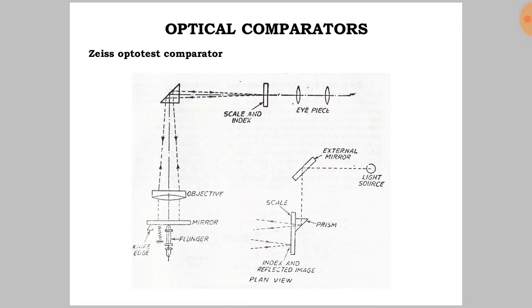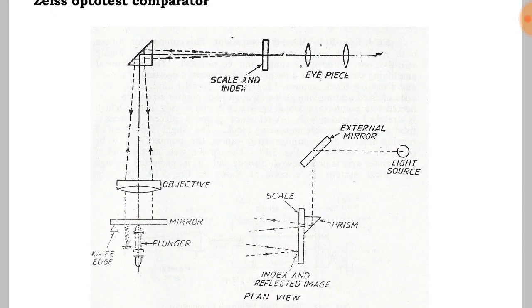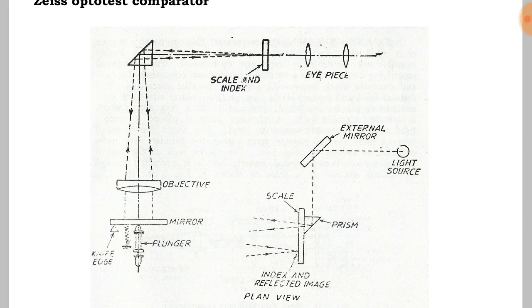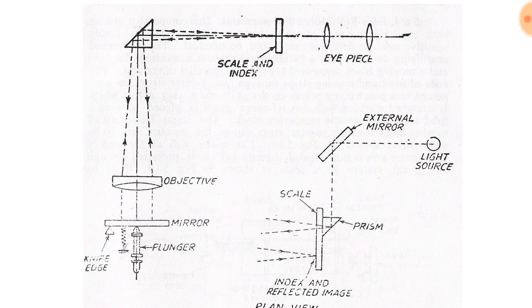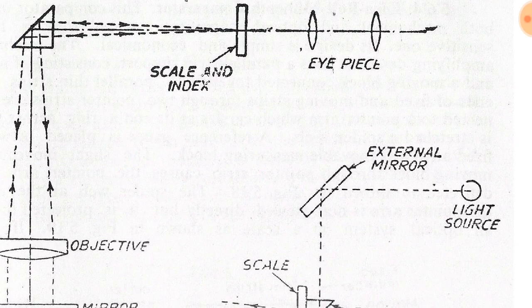A beam of light passes through a graticule suitably engraved with a linear scale, and the movement of the mirror causes this scale to move up or down past a translucent screen inside the observing hood of the instrument.